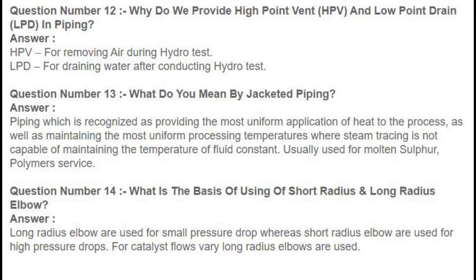Question number 12: Why do we provide high point vent (HPV) and low point drain (LPD) in piping? Answer: HPV is for removing air during hydro test. LPD is for draining water after conducting hydro test.